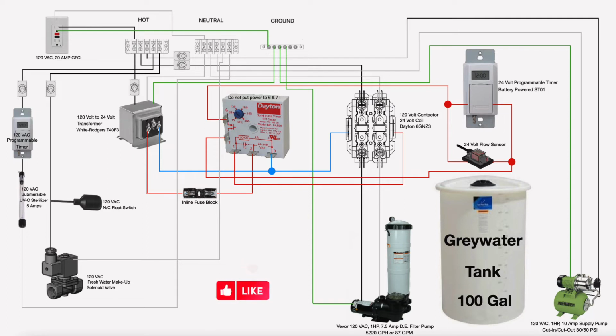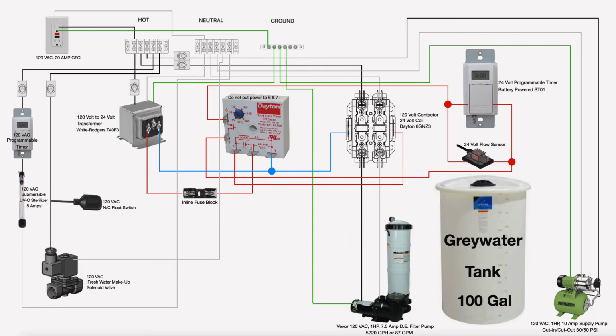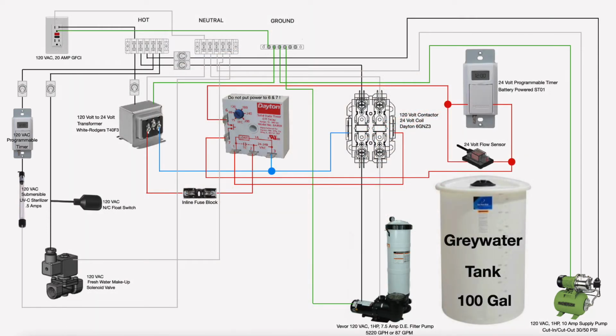Now, as far as the supply pump that supplies your toilets for flushing and filling, or your landscaping, your washing machine, your whatever industrial process, that supply pump is controlled by a pressure switch. This one happens to be set at 30 psi for cut-in, 50 psi for cut-out pressure. But there's adjustments you can make on those to fit your specific need. And you can see this even has a bladder tank where it's filled with air, and then there's water on the other side.